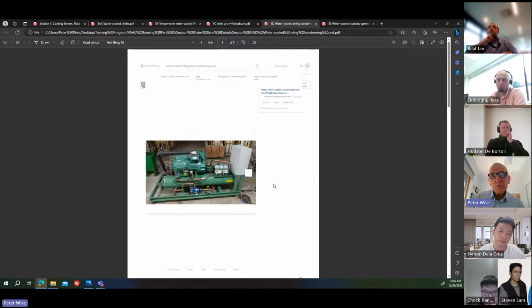If you're doing a hotel or a similar project, you might have a lot of cool rooms and freezers to reject heat from. Sometimes the mechanical contractors are involved in providing that heat rejection system for the cool rooms. So this is a water-cooled refrigeration condenser. Now, I did a job a long time ago now, but it was a big hotel, and we probably had 100 of these, which were connected to the main condenser water system. This has got a shell and tube heat exchanger, with the compressor sitting on top. Similar to a water-cooled chiller, the heat is rejected from the condenser into the condenser water system and out to the cooling towers.